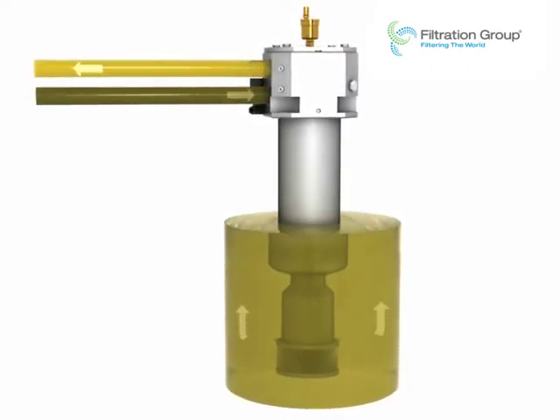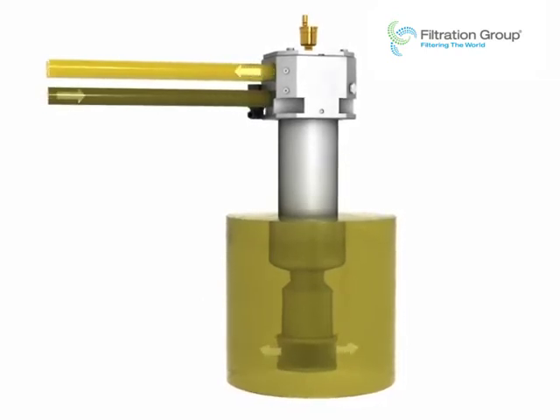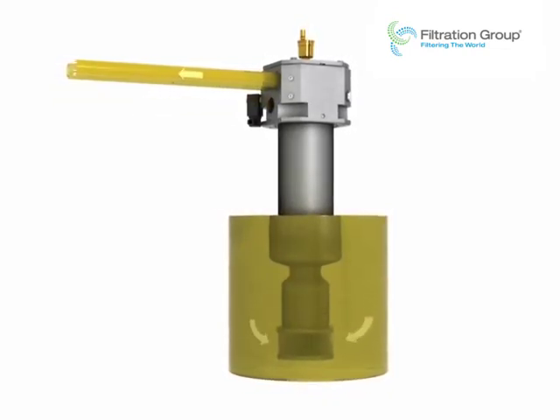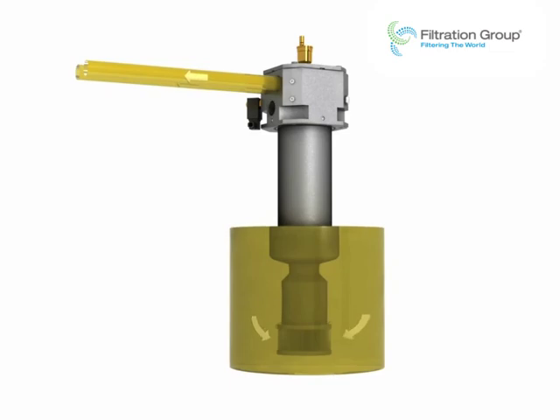As a result, oil that has undergone high efficiency fine filtration is delivered to the suction pump under positive pressure. In the event the return flow is interrupted briefly, the pump can continue to draw oil directly from the tank through a valve and a coarse protective filter.